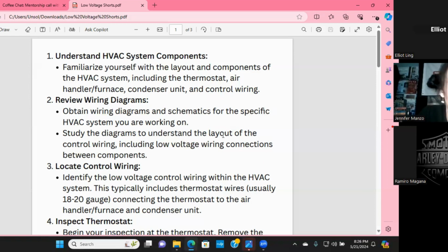And take a picture of the filter sizes to you guys and put that in there. That will help you immensely in many, many situations. I have what we call a filter book, and it's not just filters, it's filters, belts, like tags if they have a different type of contactor than normal or whatever. So that helps a lot. And then review the wiring diagram.